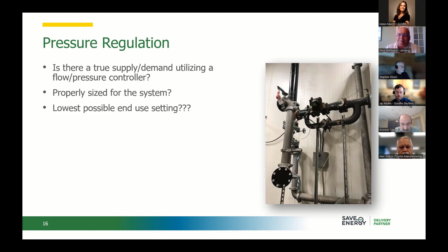Piping issues. This is a great one. I'll let you tell the story. One of my favorite ones is seeing two compressors, you can see my hands here, that had discharged together into a T basically, and they had the outgoing line, and that collision point there between the air is a major pressure drop. Well, this is a major pressure drop too, Dino.